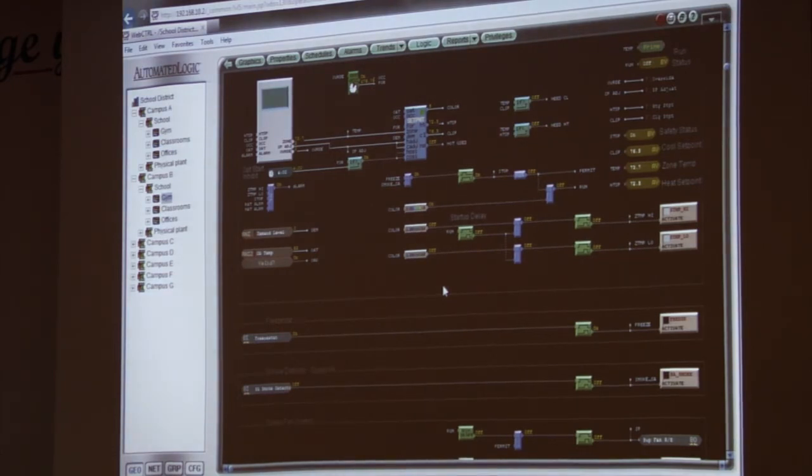On his, I know it's input 3. I'm going to walk up to his module over here, and I'm going to look at input 3, and I'm going to find out what it's on. Uh-oh. 1, 2, and look at input 3. Well, there's a paper clip in there. Oh, so we can see his freeze stats going off. So we should probably get him a screwdriver. He should get that paper clip out of there, and I bet you his freeze stat will clear.